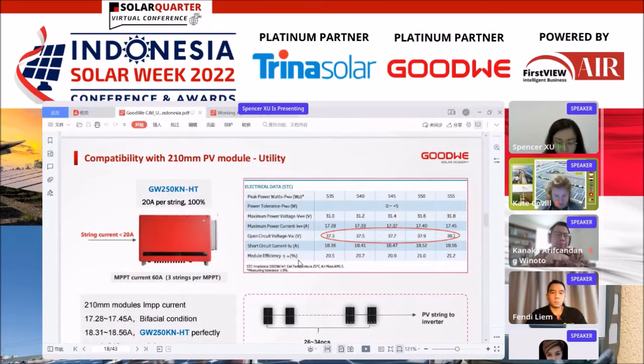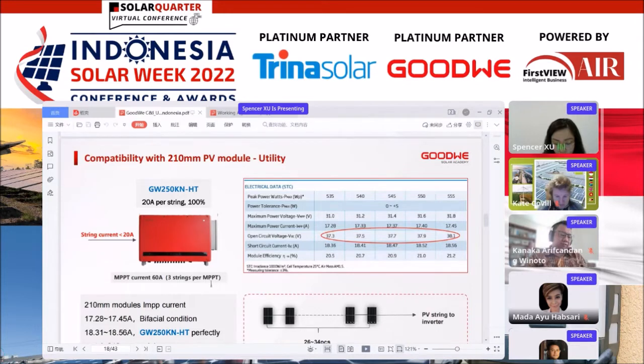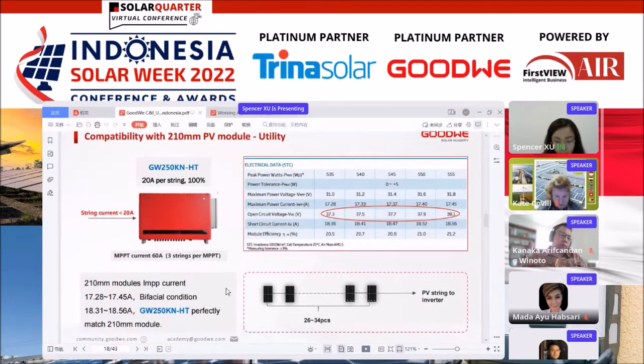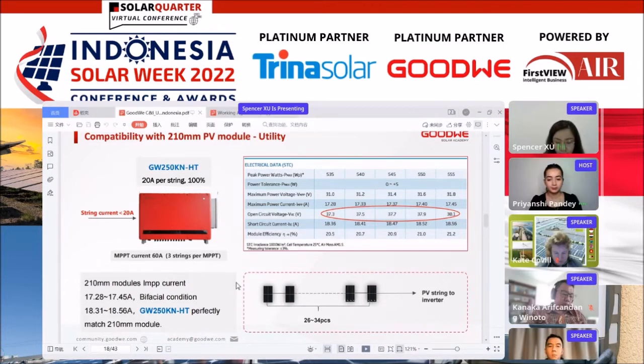While for the utility projects, as we've mentioned before, we have a special version of KNHT. So the string current of KNHT is 20 ampere, with a 3 string design. So our clients may have the concern that they will need an external fuse to meet the regulations requirements, which require us to prevent the two-string current from being backfed to the remaining string. Well, the KN series actually uses a new no-fuse design to solve this problem. It is equipped with an intelligent DC switch that can automatically trip when an overcurrent failure happens. And this DC switch can receive the trip signal from the inverter DSP to shut down the DC circuit when an emergency happens. So we can say that our new model is perfectly matched to the 210mm PV modules.